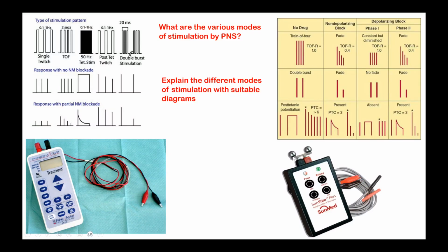For a single use, you can use this ball electrode. For continuous monitoring, you can use what is called the crocodile electrode. These two tips can be inserted into this. After pulling out this, the red can be inserted into the red and black into that. And you can use it like this. Okay, so these are the two types that you have to know.